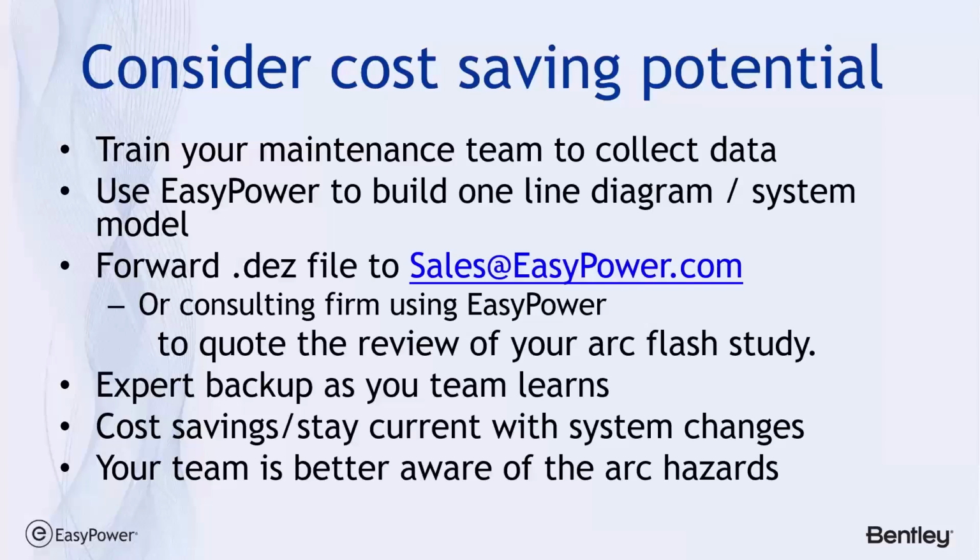And so having your maintenance people and your facility people participate in the data collection and be involved in the calculations of the arc flash, and understanding what makes the arc flash situation worse, is important. Because they have more knowledge of the system than usual consulting firms, the better trained they are in the arc flash process, the more value you get from your investment.